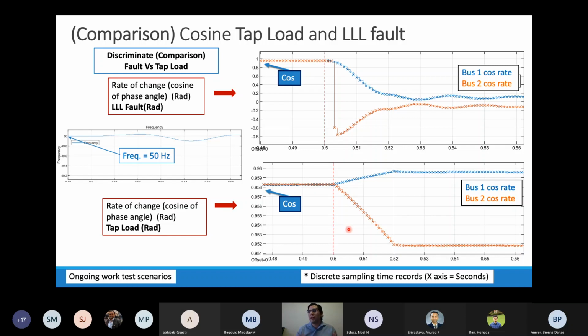Here I'm doing a comparison over a three-phase fault, to compare how a fault behaves in contrast to how we discriminate a tap load. So for the rate of change of the cosine in the three-phase fault, the event happens, and as we can see, these are the cosine responses of both ends of the line of the currents.